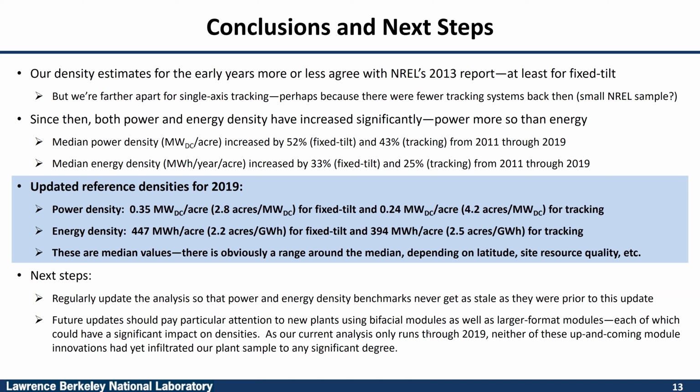But the reason you still want to go with tracking is because you're achieving that energy density with less capacity. Because the tracking plants generate more megawatt hours for each megawatt, you're able to achieve that higher energy density using fewer modules. And because modules are costly, if you can reduce the amount of capacity in the plant or the number of modules, you're better off on a levelized cost of energy basis. So that's really the reason. I didn't bring cost into this presentation, but it is sort of the missing ingredient here.